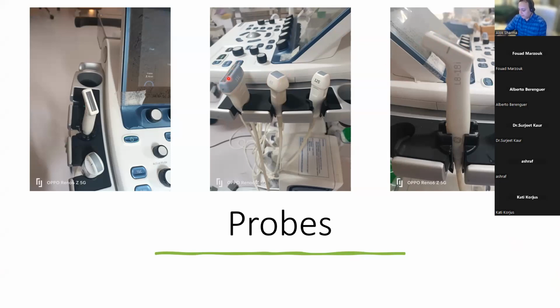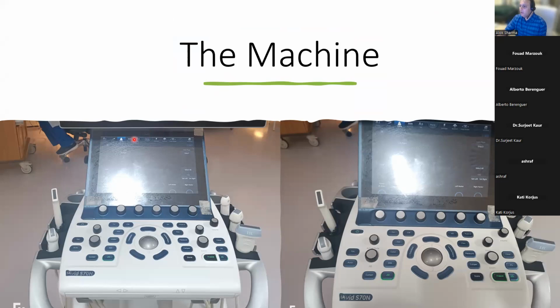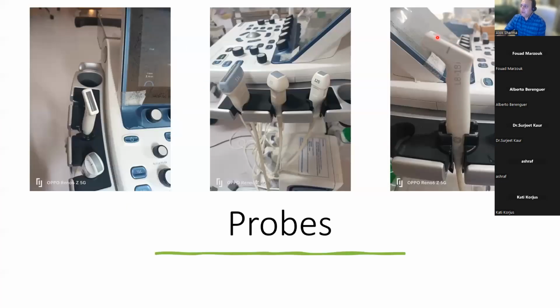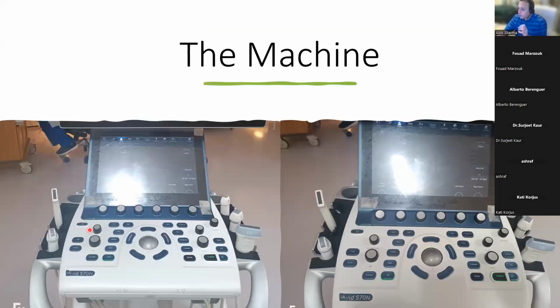So you want to uniformly apply gel, and you want to go to either a preset setting or set your settings, where once you apply this to the baby with the gel, you can then press auto gain, which we call TGC in our machine over here, and that will automatically try and compensate your gain settings. If you lose contact or you find the gain settings are very bright because the machine is having a thing, you can press it again. And especially in the GE, it usually takes 2 presses for the machine to actually delineate what the best gain is for that particular setting.